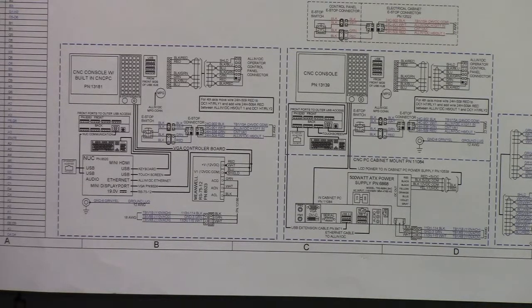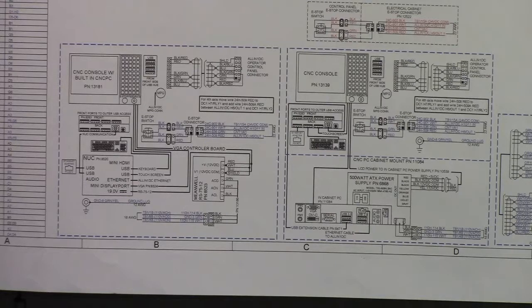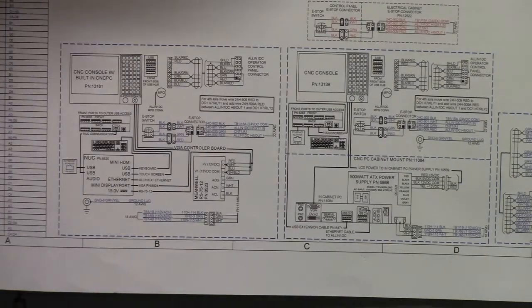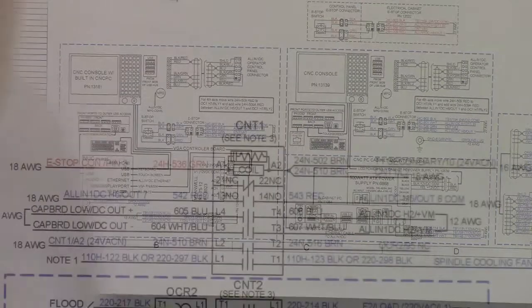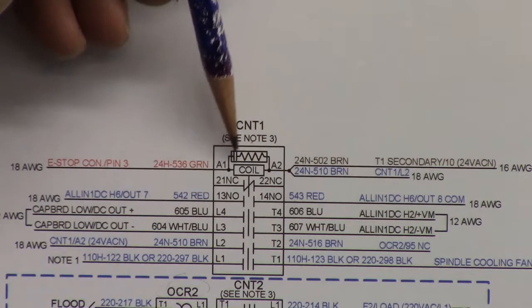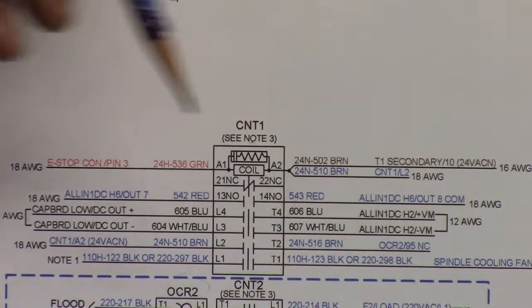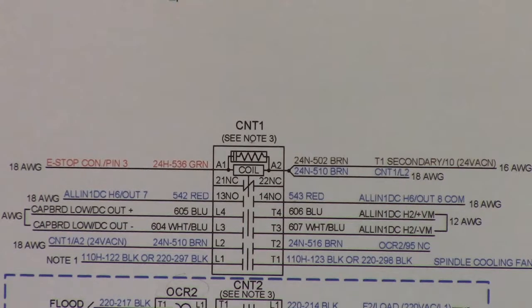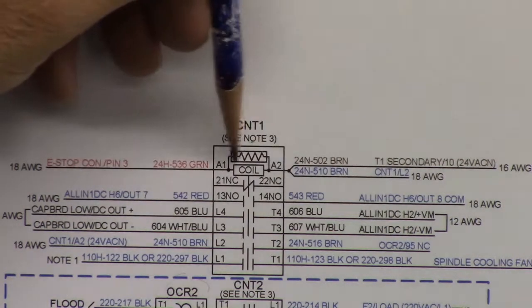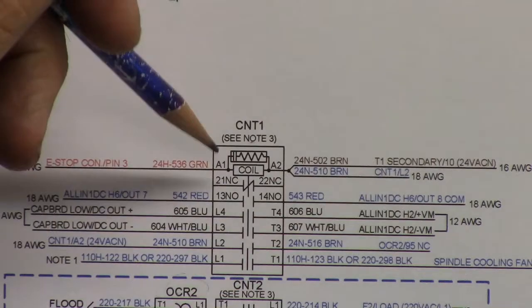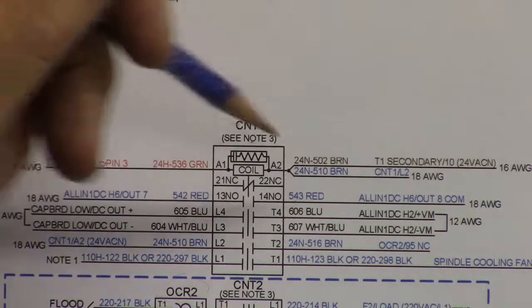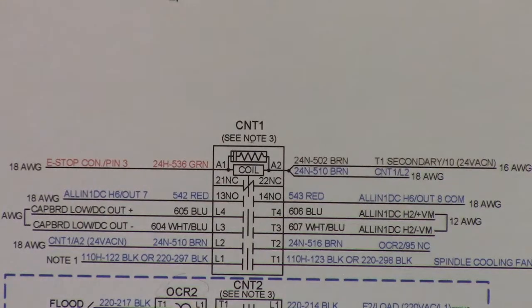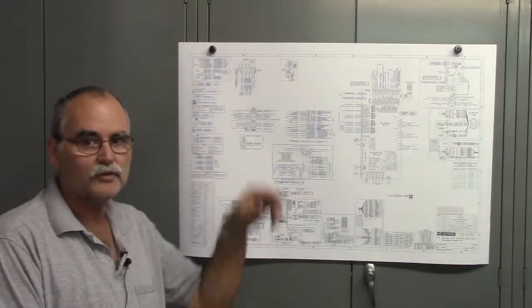I think that pretty much covers the print. Oh, the other thing we got to talk about is snubbers on relay coils. Let's go to CNT1 and we'll talk about a snubber. Here's CNT1 and here's the actual coil of the relay. And then you see this little device above it. This is called a snubber. All contactor coils require a snubber. Either the contactor manufacturers recommended snap-on snubber or Centroid part number 18-19 external quench arc snubber. They go across the coils. They're kind of suppressors and they help with noise. So Centroid wants you to put these snubbers, whether it's AC or DC, use the quench arc across your coils on any of the relays that you use in your control cabinet.